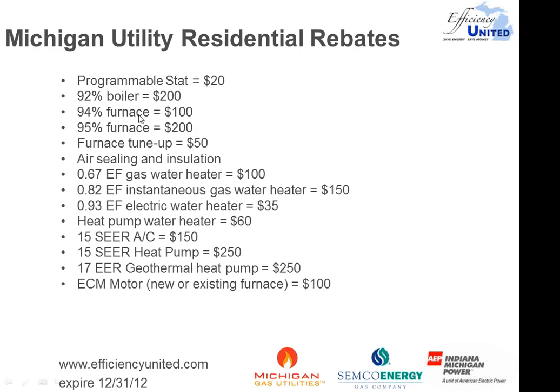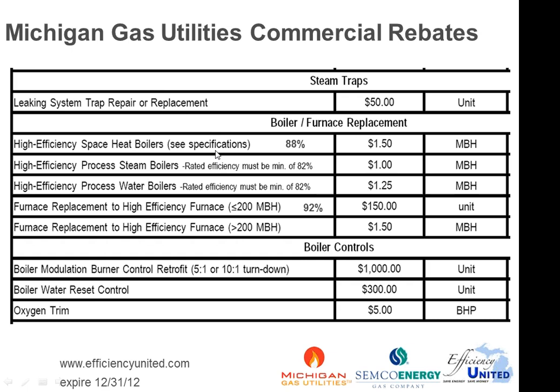If you're up in Michigan, residentially, a 92% boiler gets you a $200 rebate. Commercially, a space heating boiler has to be at least 88%, which would include all the condensing boilers, obviously, plus a few near condensing. You get $1.50 for every MBH in size of the boiler.